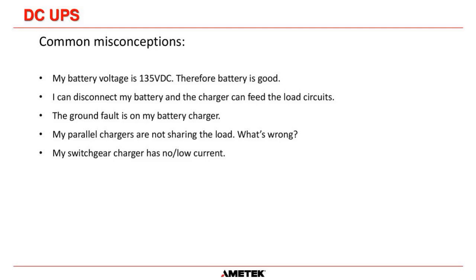In truth, it may still clear the fault depending on how high the fault is, but in doing that, it's going to reduce the output voltage, because remember, the only way that you can limit the current on a charger is by lowering the voltage. So to reduce the current, you have to reduce the voltage. And when you reduce the voltage, you can affect everything else that's connected to the system. So that is why you should not disconnect a battery from a DC system.